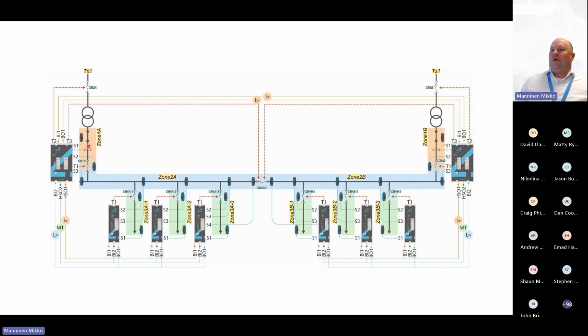So current is typically monitored from the main incoming breaker, and that relay here is monitoring the current, and it also receives the light signal from any of the subunits or from its own sensors here. The main thing for the relays here is to trip the main breaker, the upstream breaker, and the tie breaker to isolate this left side if the fault is here on the left side.